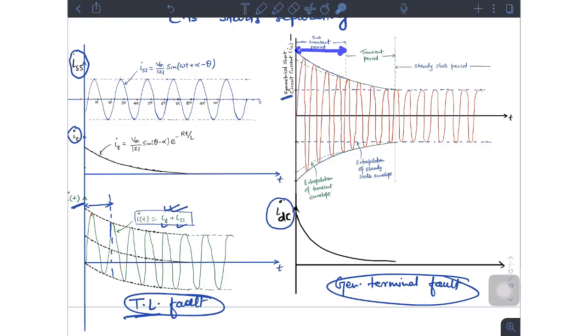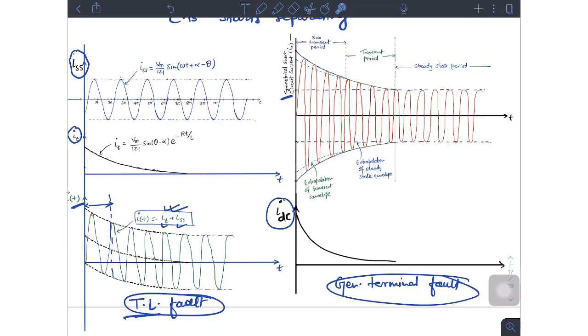During the sub-transient period, the current magnitude consists of the sub-transient symmetrical short circuit current plus the DC offset current component — both together give the total current. So just after the occurrence of a fault, the current flowing through the circuit breaker will be: the sub-transient part of the symmetrical short circuit current plus the DC offset current.